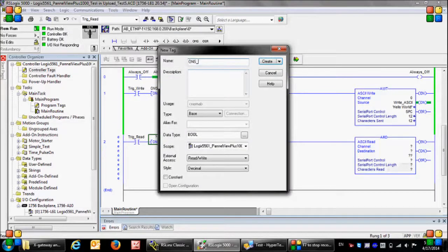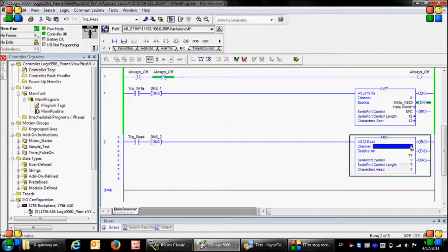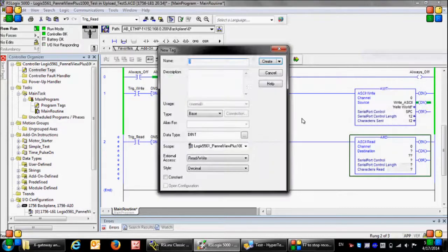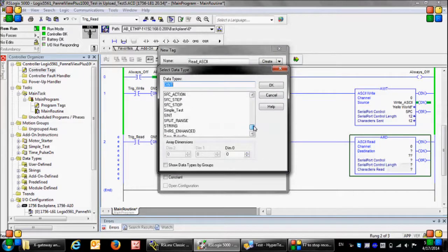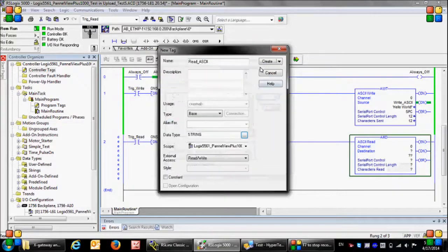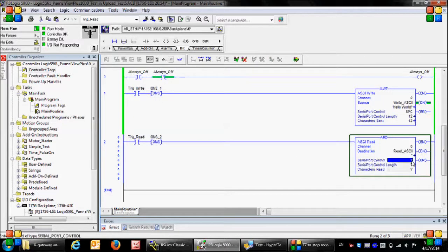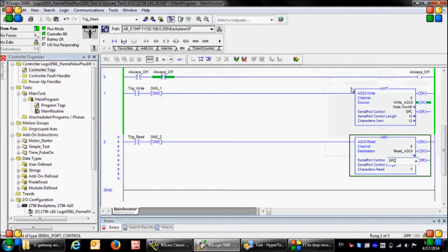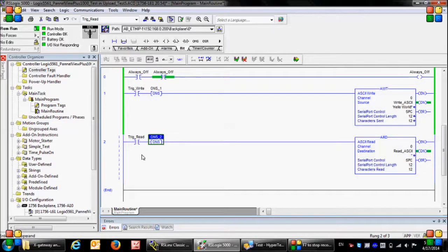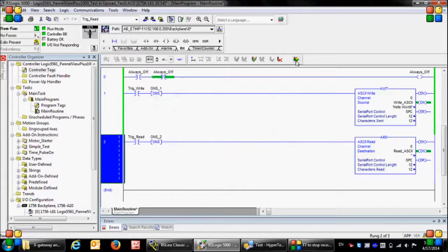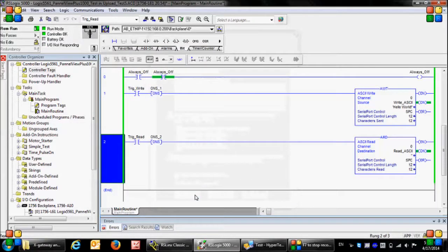And for the ASCII read instruction, for the channel number zero, destination again is a variable of type string in which the received message is stored. So here I change the type to string, and for the serial port control I'm going to assign the existing tag SPC. Now let me download the new rung to the PLC.